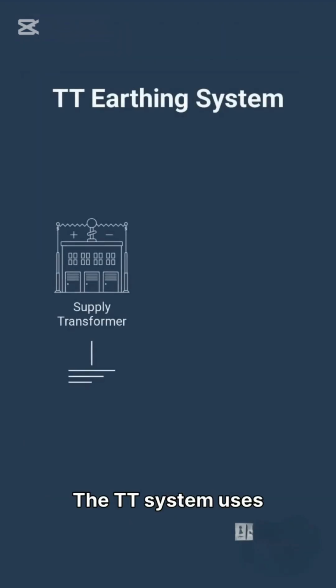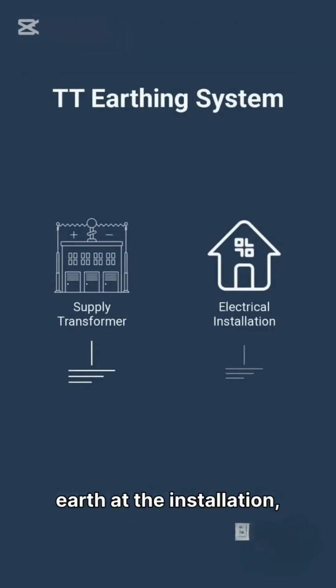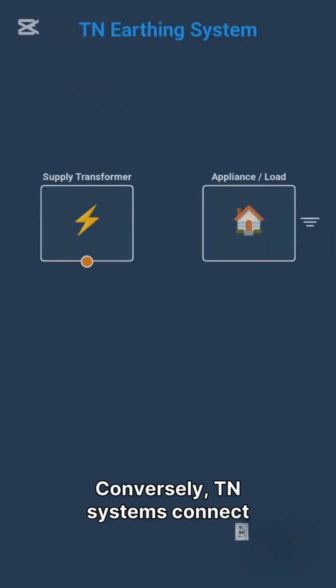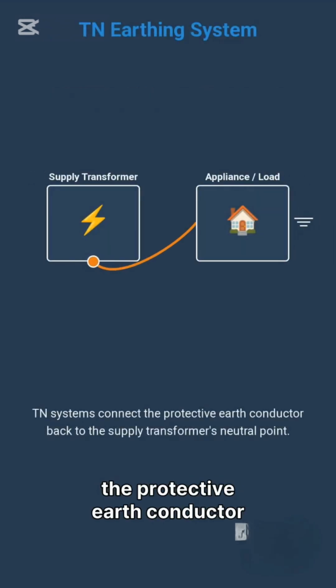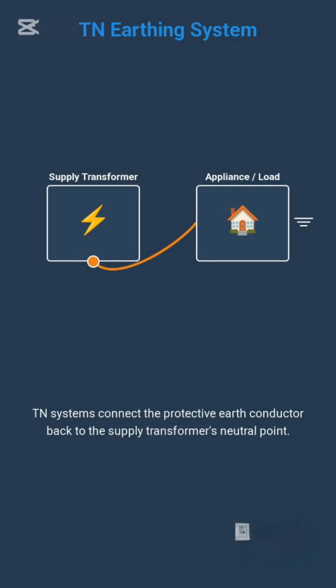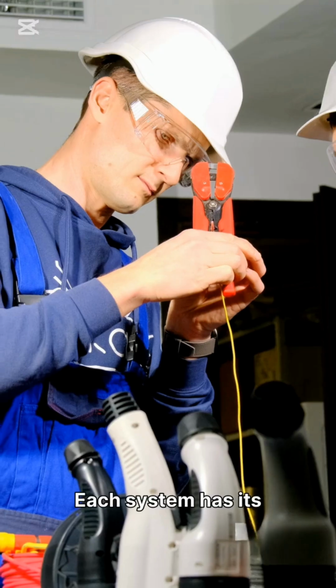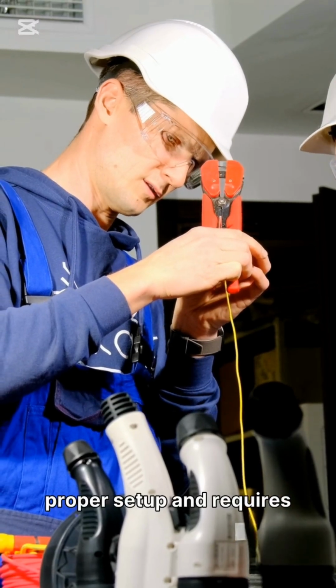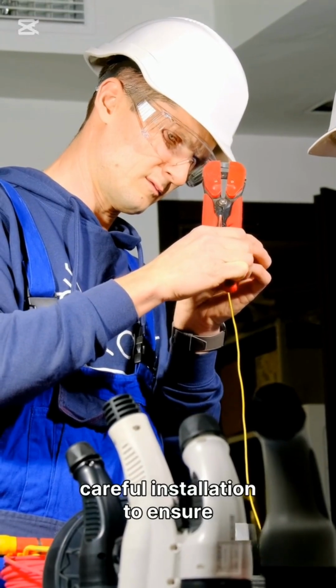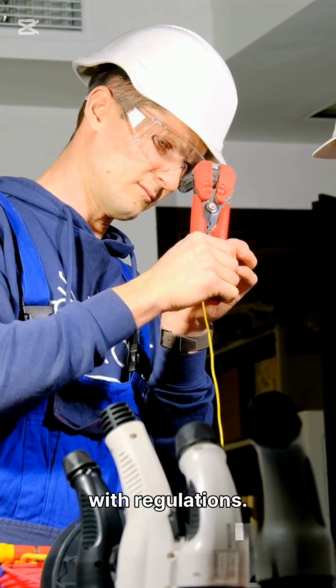The TT system uses a direct connection to earth at the installation, independent of the supply network's earthing. Conversely, TN systems connect the protective earth conductor back to the supply transformer's neutral point. Each system has its proper setup and requires careful installation to ensure maximum safety and compliance with regulations.